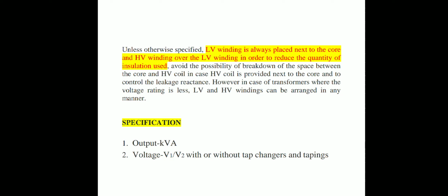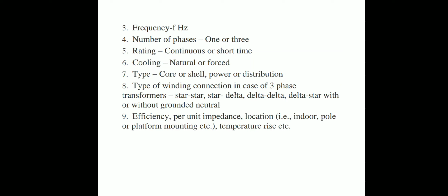Now let us go for the specification. Output is your kVA, voltage V1, V2 with or without tap changers and tappings, frequency F Hz, number of phases, obviously it would be single phase or three phase, it will be specified where it is necessary, rating, continuous or short time, cooling, it will be of natural or forced cooling, type, core type or shell type, power type or distribution type of transformer.